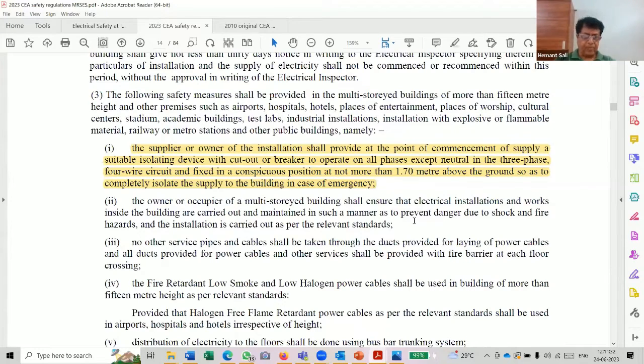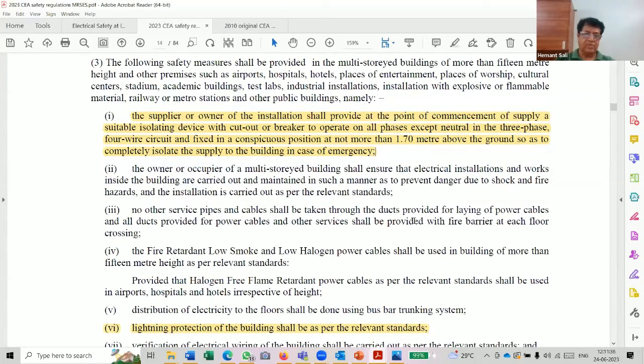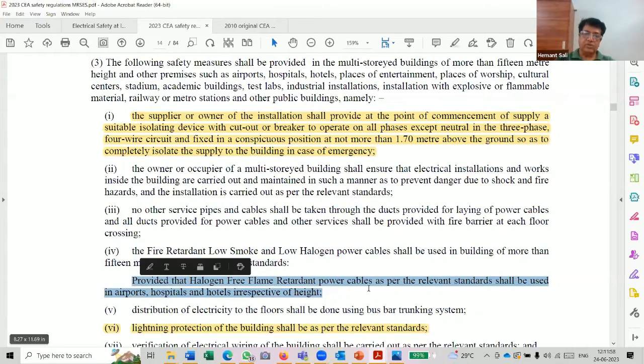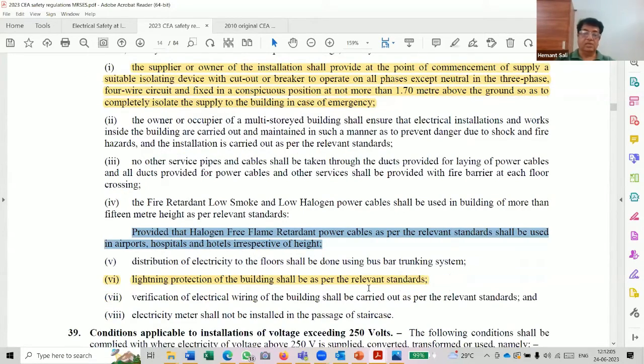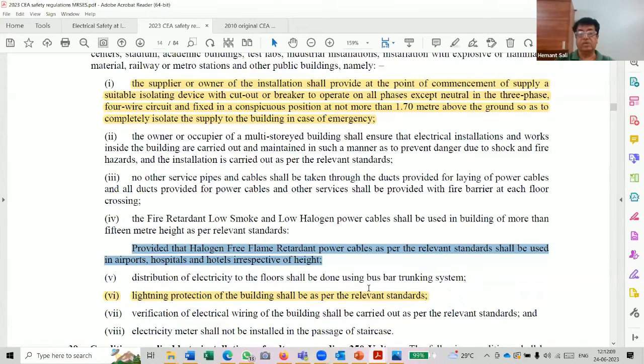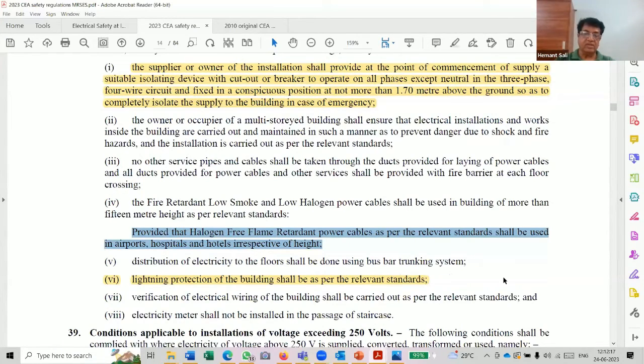Another thing is regarding fire retardant low smoke cables. I think they have mentioned FRLS cable for high-rise buildings, but at least the wording should have been that FRLS cable shall be used, because HFFR cables are also there, and use of HFFR cable is specifically mentioned for certain types of buildings. So it shouldn't be like that. One more part which could have been added is AFDD, because in the National Electrical Code, we have already given a suggestion to make a provision for AFDD. That is very much needed in the case of high-rise buildings. So I think a few things are still required in this regulation, which should actually be necessary from the point of view of evacuation processes and all that.